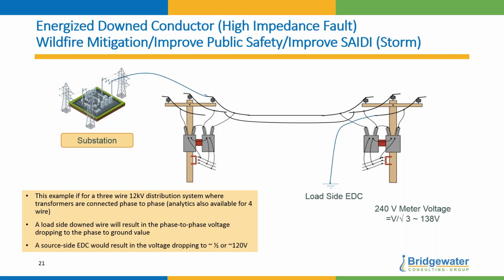So when a wire goes down on a 3-wire system, you're looking at an example of a 12 kV, for example. There's the load side wire down. When the load side wire is down, those meters that are connected to transformers don't go to 0. They go to the square root of 3, or if you're a 240 volt meter, it goes to 138 volts. If it's a source side, on the other side, it's a voltage divider, and the voltage will go down to 120 volts, or thereabouts. Now, it's not exact, right? It can go down to 130, 150, whatever it is, but it's an indicator that you have a wire down.